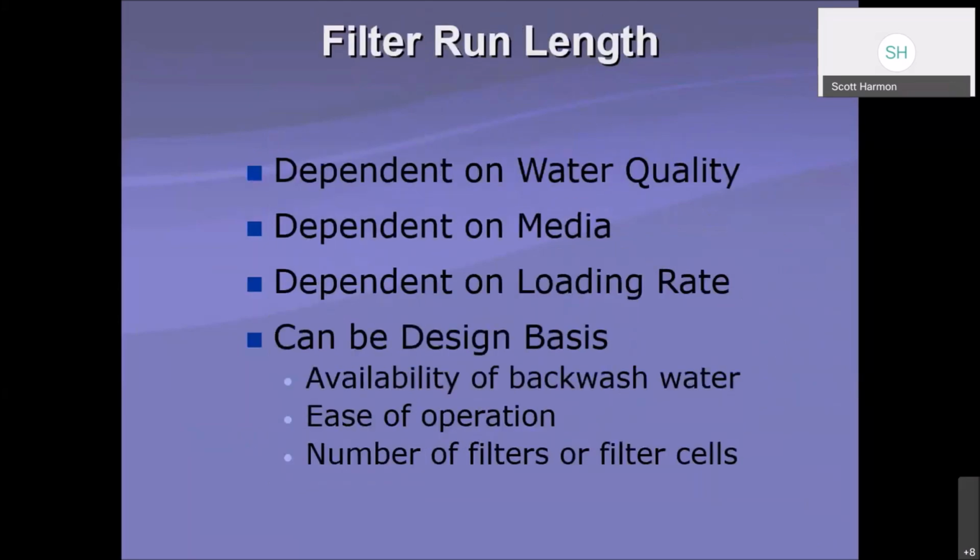Filter run length, very important in our industry, right? We don't want to be clogging our filters up and having to wash them more than necessary. So we try to get as much treatment done ahead of the filters. Filter run length is going to be dependent on the water quality, depending on the media, how much media you have, what type of media, those types of things. It's also going to be very dependent on the loading rate, how much material is going into them, right? How much are we removing ahead of the filters, which is a big factor in how long your filter run length will be.